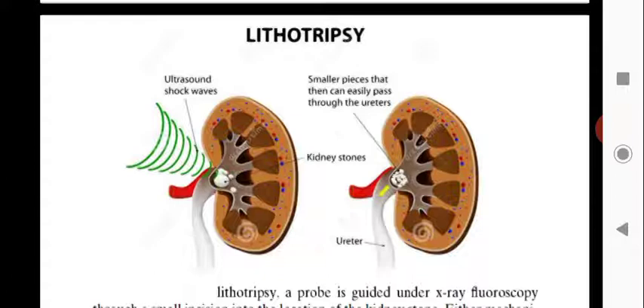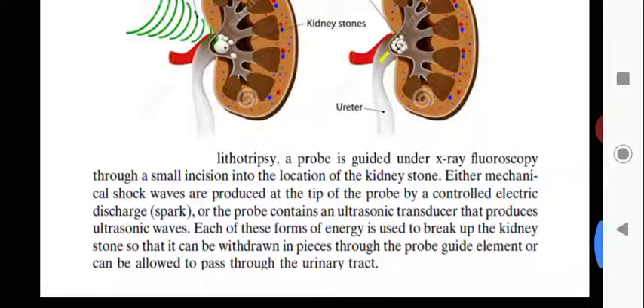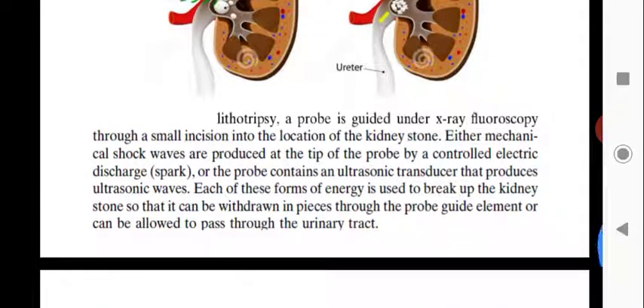Ultrasound shock waves break the stone into small pieces that can easily pass through the ureter and then through the urine. In lithotripsy, a probe is guided under x-ray fluoroscopy through a small incision to the location of the kidney stone. Either mechanical shock waves are produced at the tip of the probe by a controlled electric discharge spark, or the probe contains an ultrasonic transducer that produces ultrasonic shock waves to break up the kidney stone so it can pass through the urinary tract.